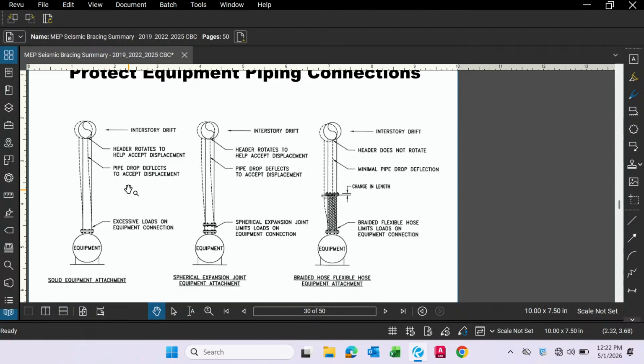Here's the braided hose, the flexible braided hose. The only problem is it only flexes in one direction, and when it flexes, it shortens, which pulls down on the pipe header above. So if you use this type of flexible braided hose, consider the drop in the header pipe above - you probably want to put a spring hanger or something up top to allow for that dip in the pipe elevation. Mason makes both of those options, the braided or the rubber.